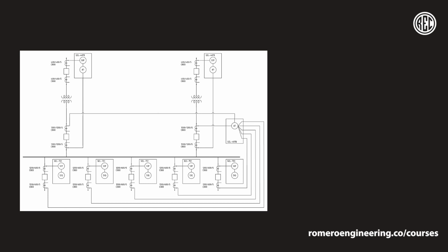And of course, we know that in reality, CTs won't replicate currents with 100% accuracy. Nothing in engineering, as we know, is perfect. So the current that the CTs replicate is not going to be 100% accurate. There are always going to be errors in CT secondary currents. In other words, when we convert from primary to secondary using a CT, the secondary is not going to be an exact replica of the primary current scaled down.